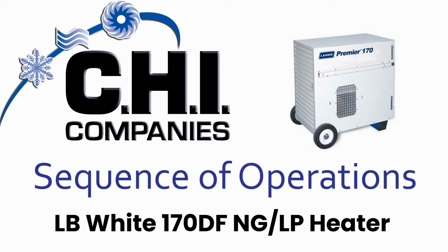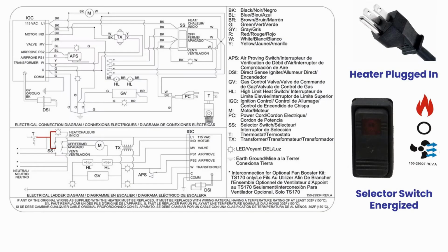In this video, we'll be defining and reviewing the sequence of operations for the LB White 170,000 BTU heater. These units have a three-way selector switch. When the switch is up, the heater will try to produce heat.